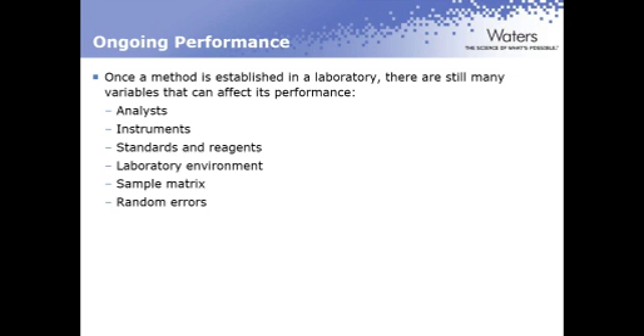The laboratory environment, as we discussed, temperature, humidity, instruments are susceptible to that. Okay, another variable could be sample matrix. The analysis of a wastewater sample could provide variability in things that are different from a drinking water matrix or a surface water matrix. And then you have those random errors that you need to deal with. Okay? So there are a lot of variables that you need to deal with in your ongoing performance. Okay? To help out with that, we need to make sure that we've got routine QC going on. So with respect to that, talking about calibrating, make sure that your calibration standards are fresh. Make sure that they're from a trusted source. Make sure that they're traceable. All this can be accomplished by using CRMs.